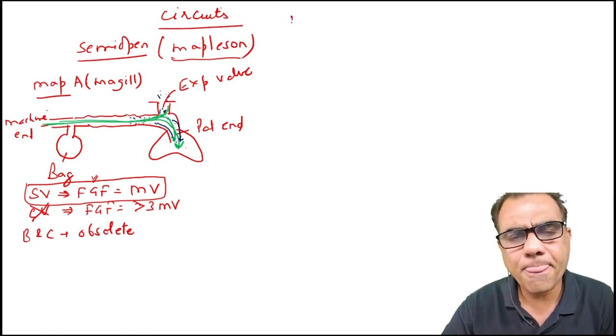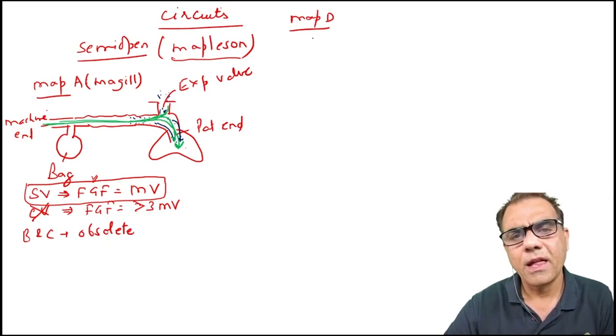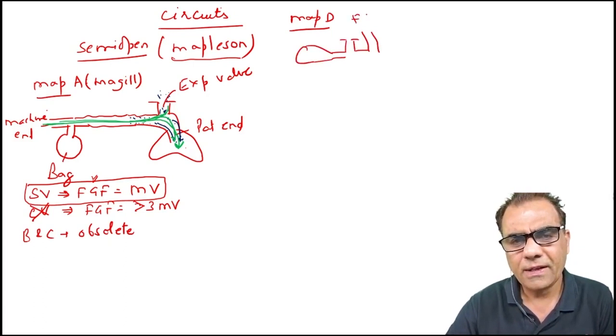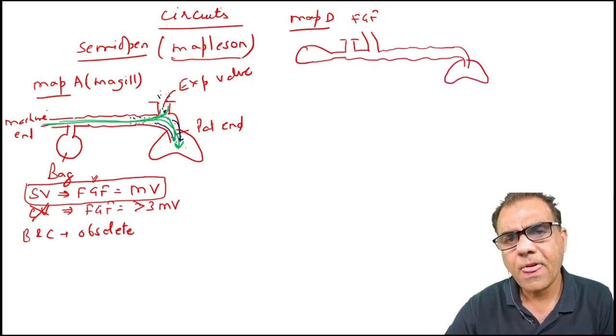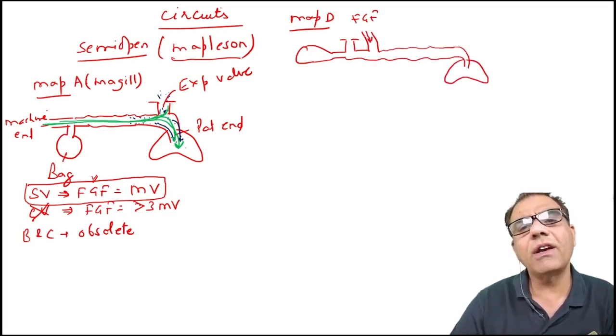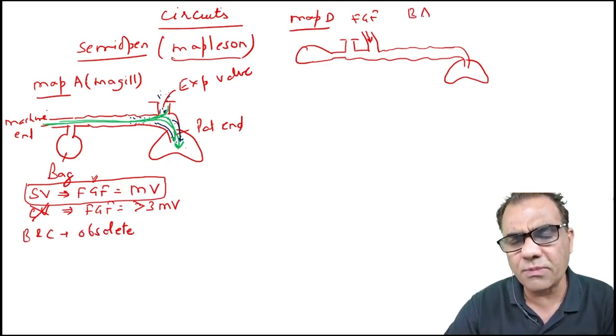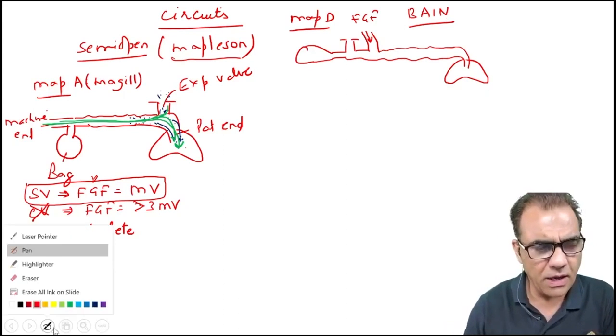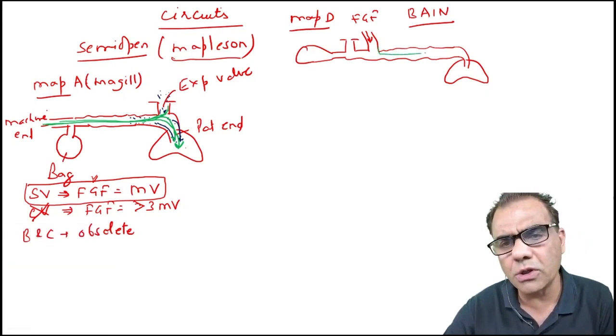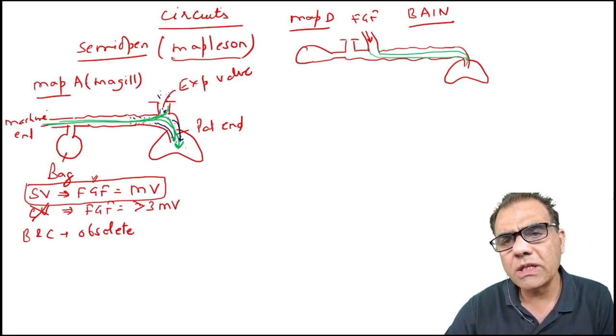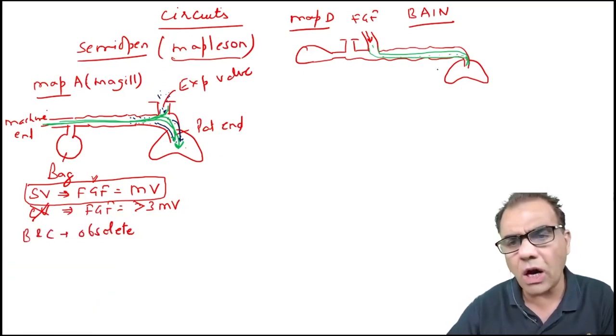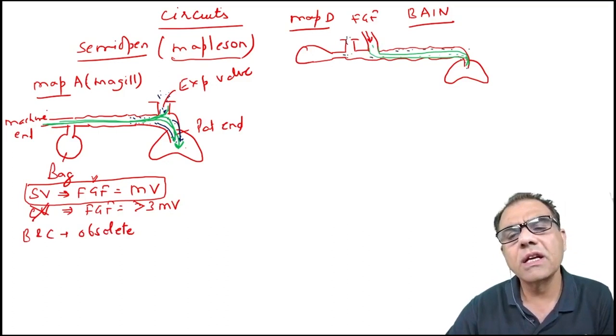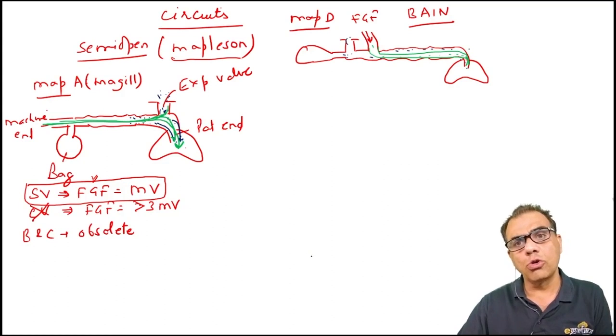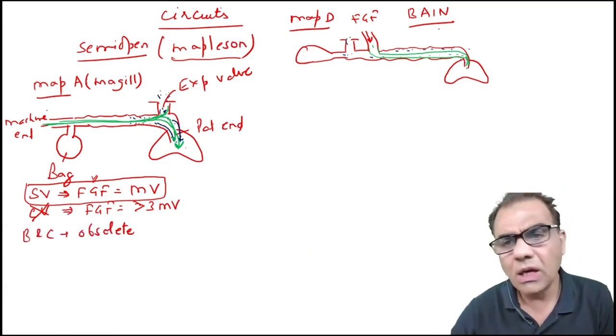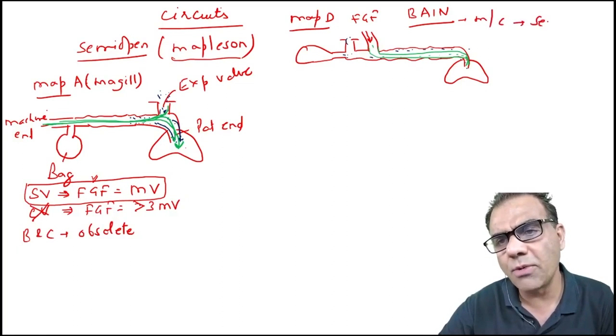Now Mapleson D is like this. This is for fresh gas flow. Now fresh gases will go through this. However, it was not effective, but a modification in this was made by scientist Bain. And what modification did he make? He actually incorporated an inner tube into this outer tube. Now you can see that fresh gases will go through the inner tube and expired gases through the outer tube. So there is no mixing of gases. That's why this circuit became very popular, so that you can say that Bain's is the most commonly used semi-open circuit.